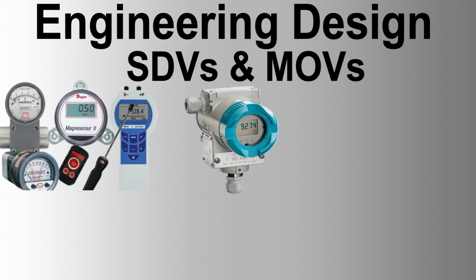Local indications. Beacon-type local valve position indication shall be provided. Partial stroking devices are required on shutdown valves as specified in data sheets. Partial stroke testing shall be performed by the control system automatically at a predetermined time. ESD commands shall override partial stroke testing.